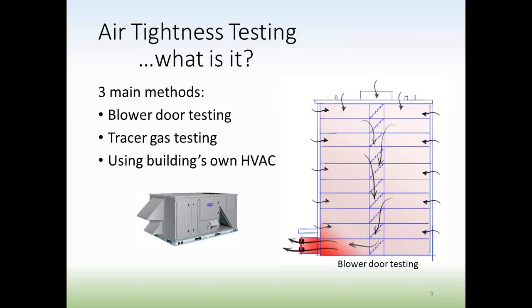Another method is using the building's own HVAC system as the blower door apparatus. You use the air handler to pressurize the building and then measure the air going into it to find out how airtight the building is. I personally don't think it's the way to go for Australia because it turns out to be pretty complicated. I've done many hot wire and pitot traverses of ductwork trying to get airflow measurements and then coordinate that with measuring the pressure differences on a big building. I think it's beyond the expertise of most testing firms here in Australia, and blower door testing is a lot more straightforward.